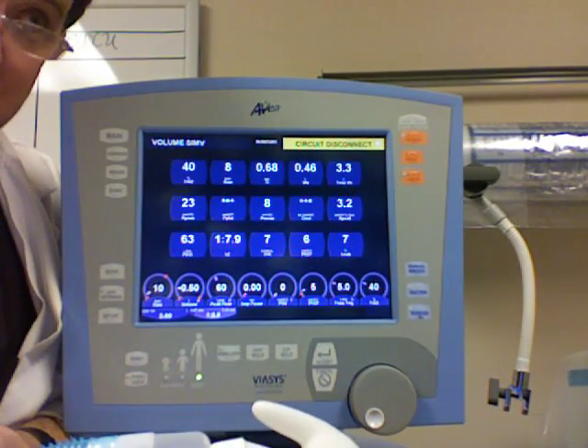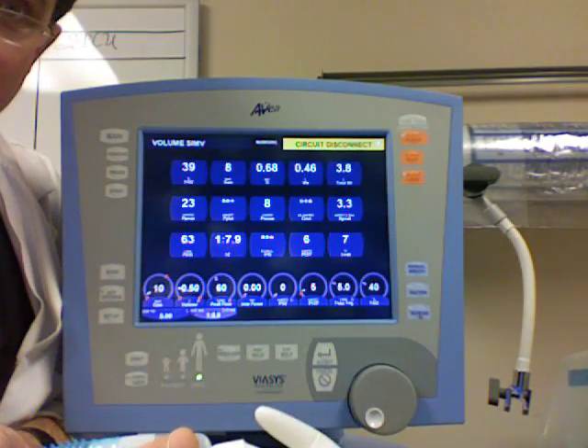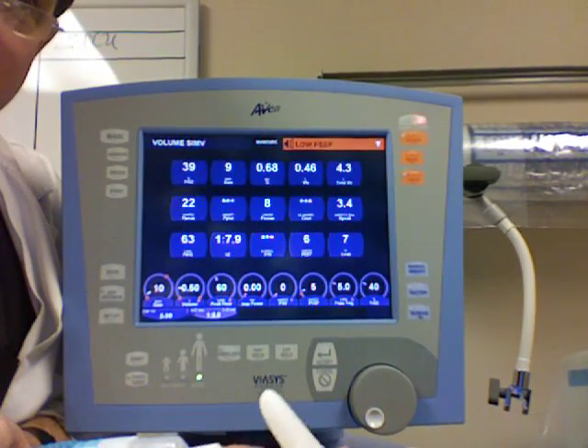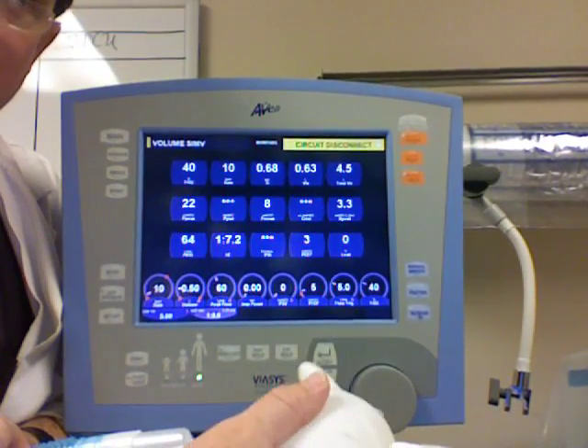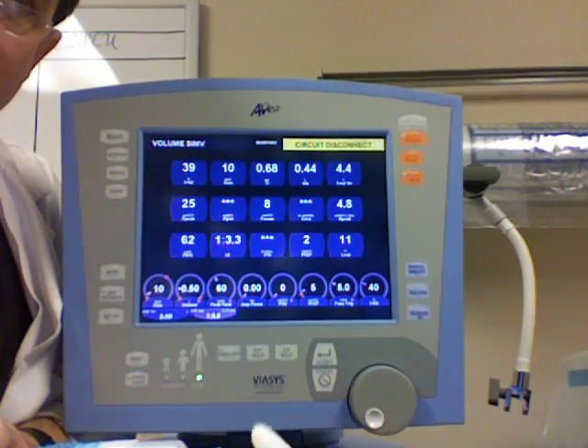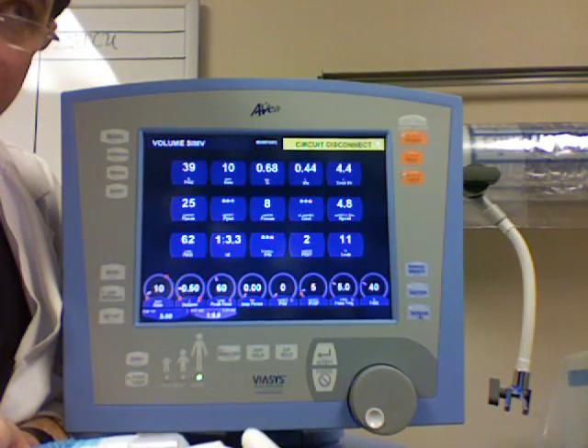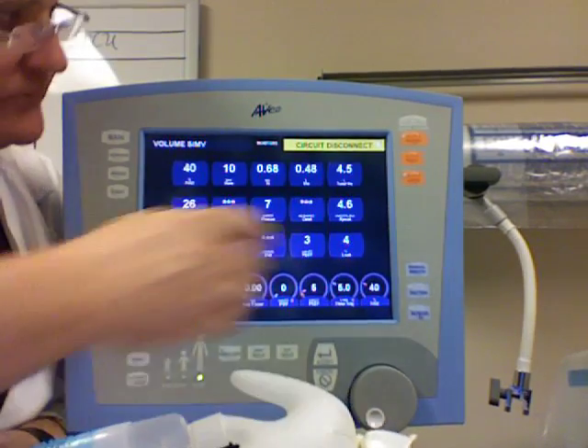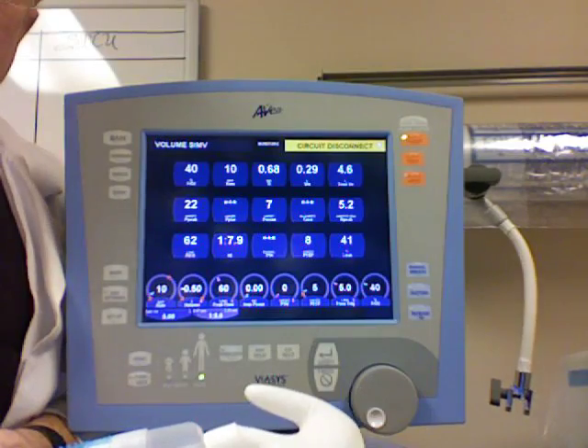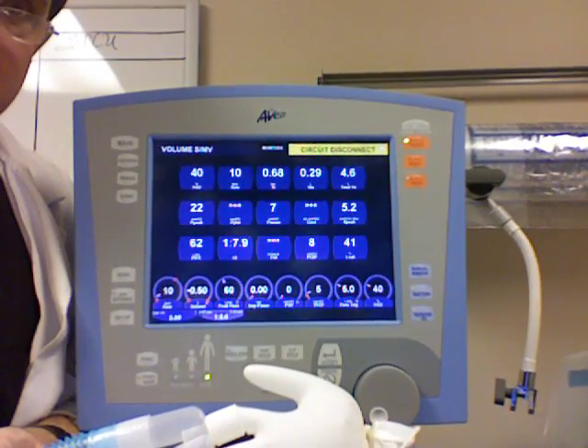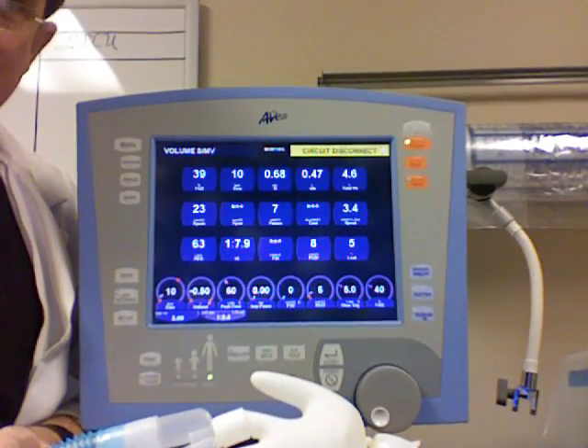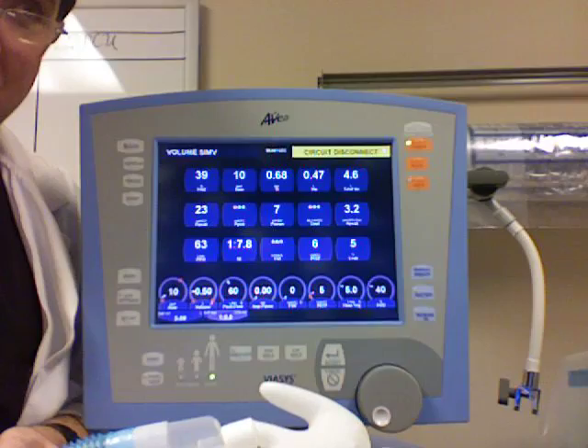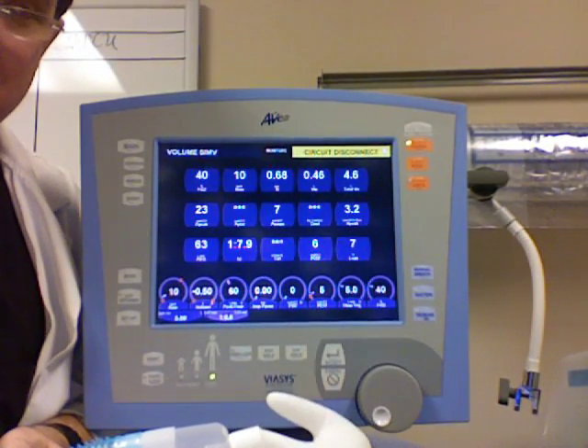In assist control, if the patient took a spontaneous breath, it took over and delivered the tidal volume at the peak flow rate. What does it do in SIMV? It's just like a CPAP breath — it kind of ignores the patient and lets them breathe on their own. So you don't get the set tidal volume on a spontaneous breath in SIMV. In assist control, the ventilator controls each breath with 500 cc's at peak flow rate, so you're not really finding out what the patient can do without the benefit of the machine.